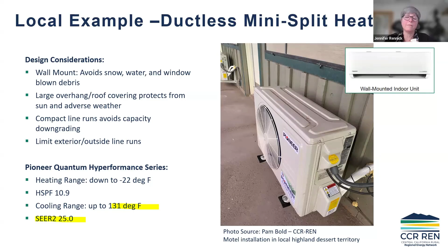And then other design considerations are wall mounting, or mounting so that it avoids the snow, water, and wind-blown debris. Putting it under a large overhang or roof covering protects it from other adverse weather. And then use compact line runs to avoid capacity downgrading, because as the temperature gets really high outside, the capacity drops when you need the capacity to get higher. Same with the cooling. So keep your indoor units compact, close to your outdoor unit, and get the lines immediately inside the envelope, and don't run your lines outside the house like you would commonly see in the coastal regions.